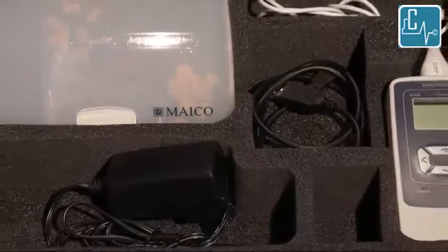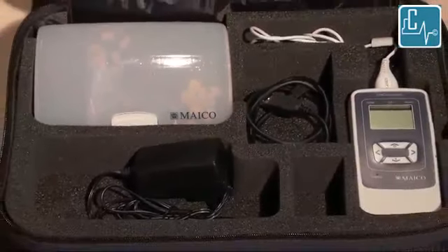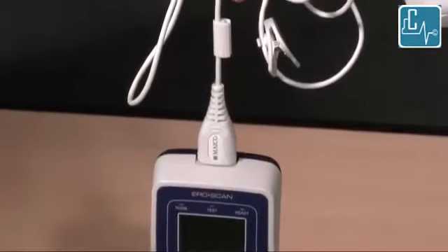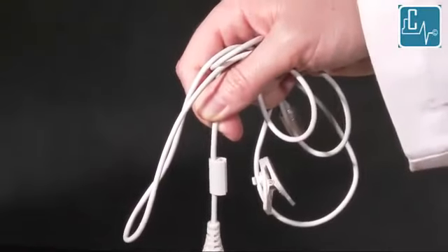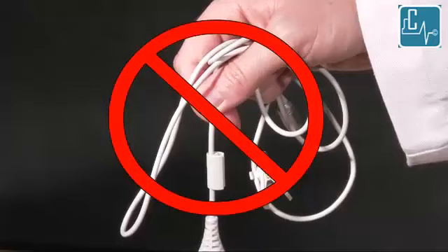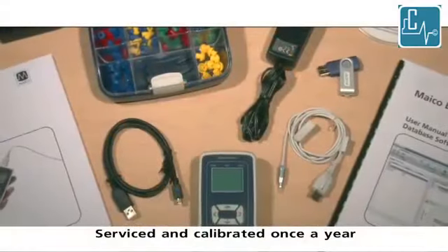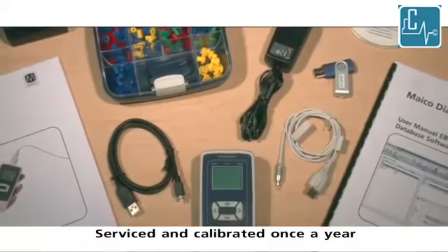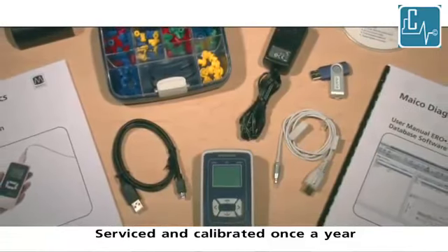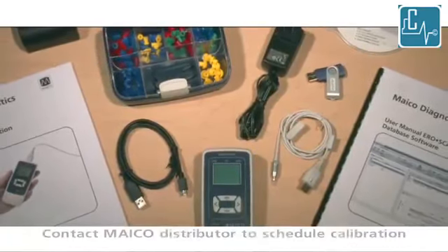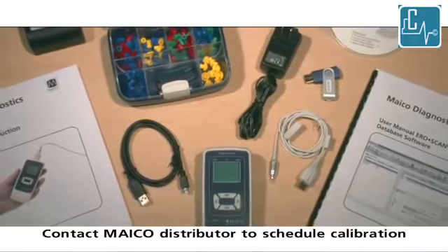All pieces should be carefully placed in the carrying case for transport. When packing the unit into the case, avoid tightly wrapping the cords or picking the instrument up by the cord, as this will cause additional wear and tear and strain on cords and connections. It is recommended that the ERO SCAN be serviced and calibrated once a year to ensure proper function and accuracy. Contact your local MAICO distributor to schedule an annual calibration.